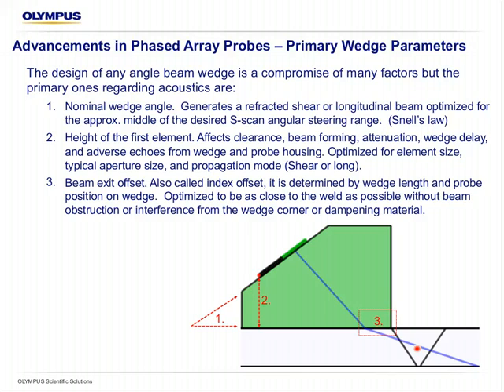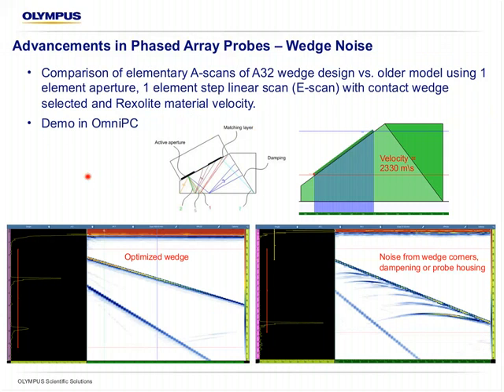There are Olympus probes and wedges that will allow the operator to program a beam that obstructs it partially because of this corner. And that's okay as long as the operator is aware of it and can move it back a few elements. So all of these three design parameters and many others were taken into account using the best and worst of Olympus probe manufacturing to overcome some of those issues for a better design.